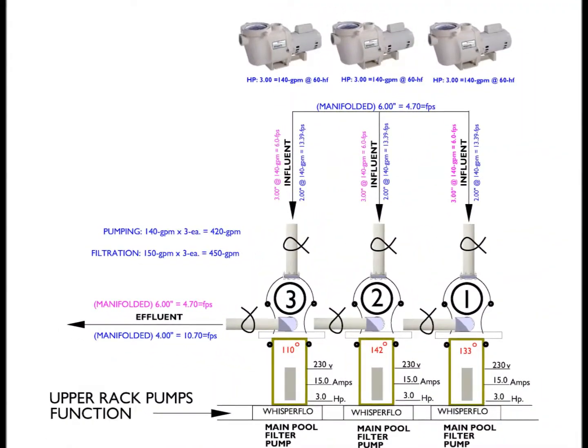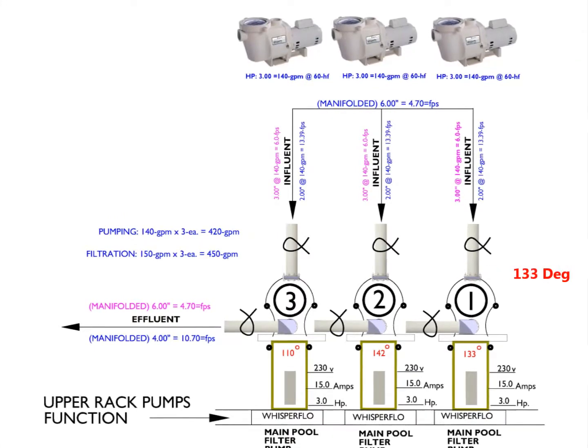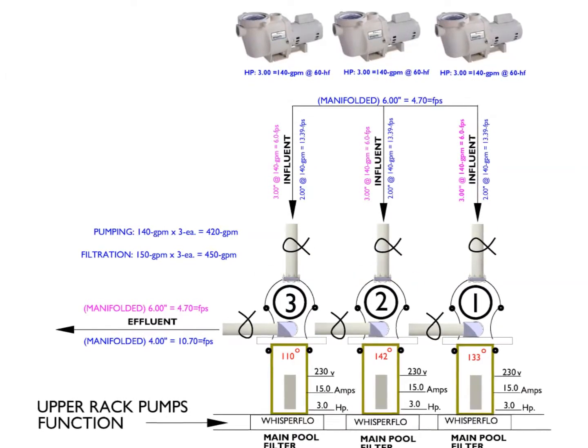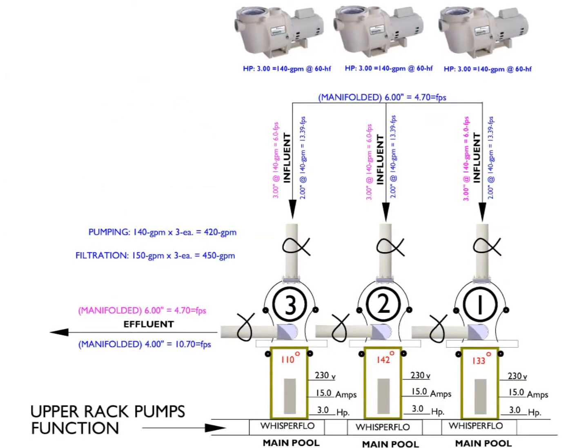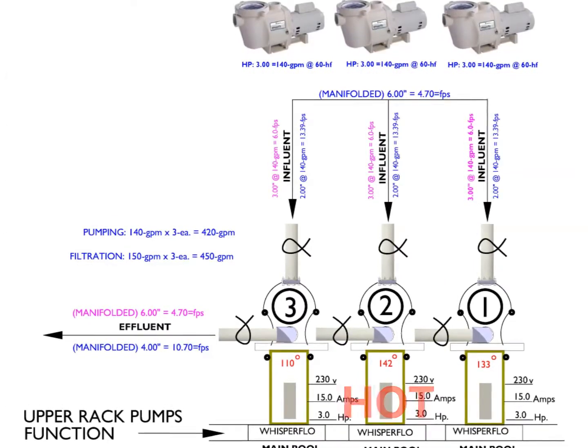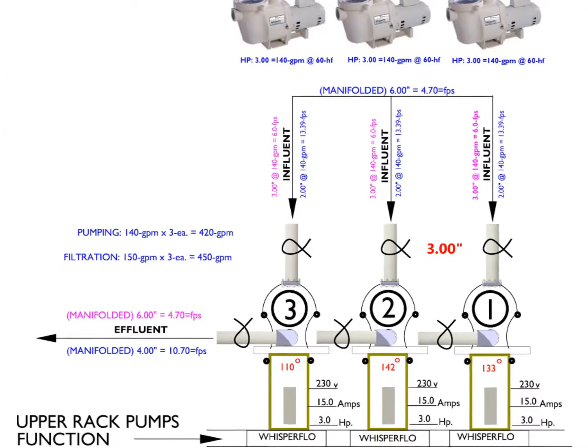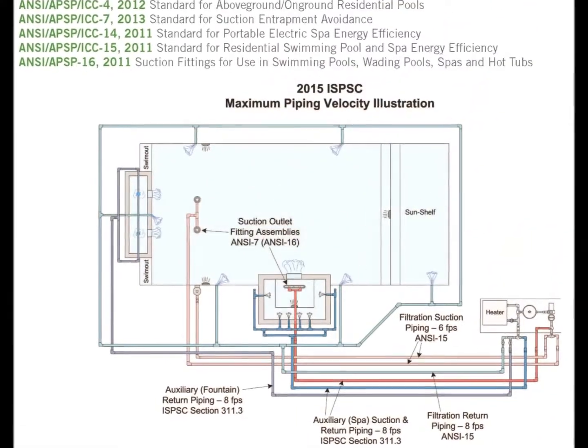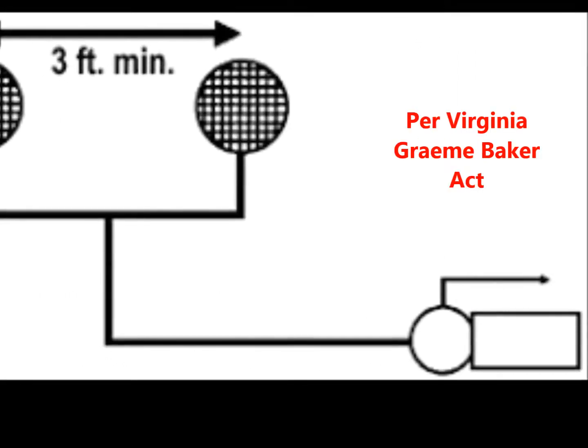Taking a closer look at these pumps, the operating temperature of pump number 1 is 133 degrees, pump number 2 is 142 degrees, and pump number 3 is 110 degrees. Assuming the published manufacturer's flow rates shown on the pump curve data, one possible influence for these pumps running hot corresponds to effluent and influent pipe sizes being out of balance with industry standards for a maximum velocity of 6 feet per second on suction lines and 8 feet per second on return lines, in accordance with the Virginia Graeme Baker Act safety standards.